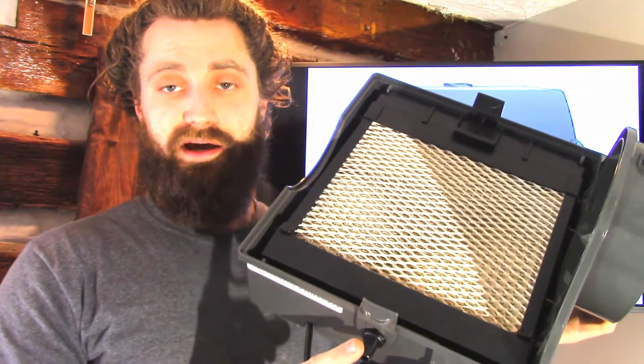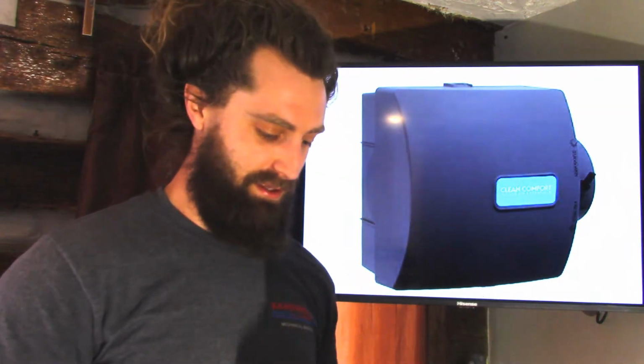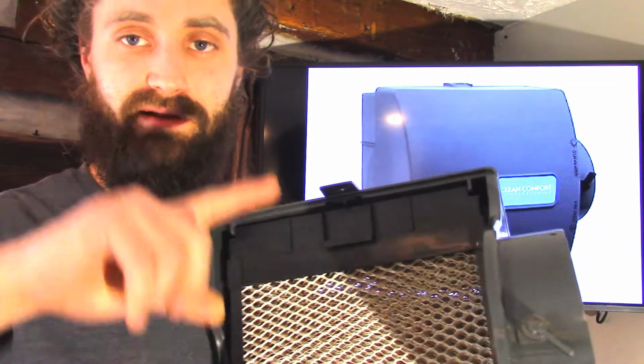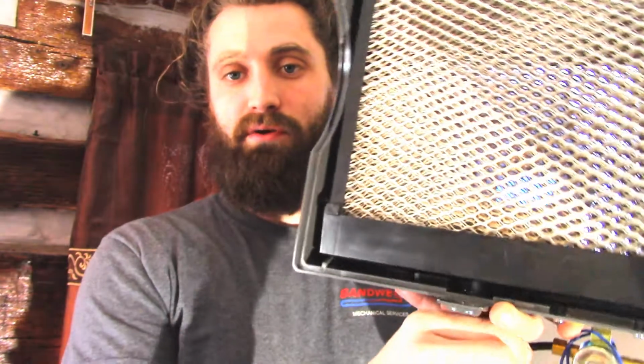On the drain side, it's very important that if this is being drained into a condensate pump, that pump is not directly piped to the outside. I've seen this many times where the humidifier drains into a condensate pump, which goes out through the foundation wall, and then I get a call in the middle of December or January when it's 5 degrees outside and there's a mess in the basement. The reason is that little vinyl hose sticking out the foundation is frozen solid. It's not an issue in air conditioning mode, but this thing produces water all winter long, and we don't want that water to freeze. So this has to go into a drain in the basement—a floor drain, sump pit, or something like that. If it's going into a condensate pump, that pump has to dump somewhere it won't freeze. Be mindful of that.